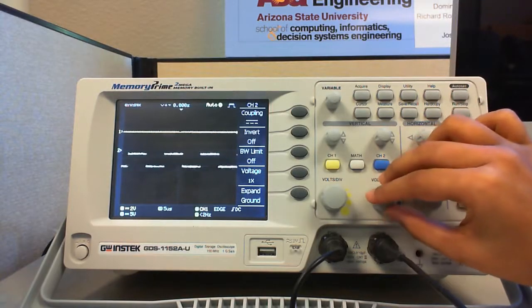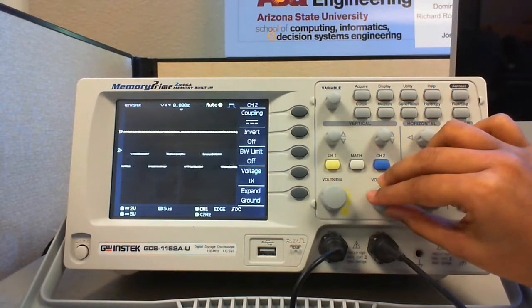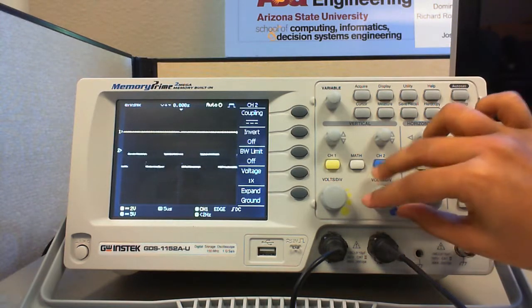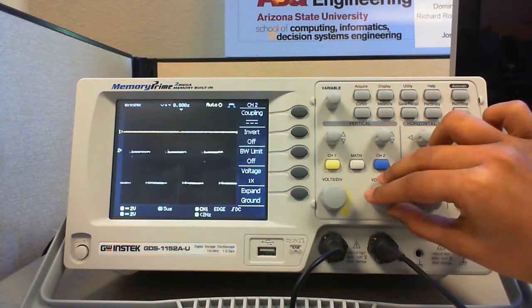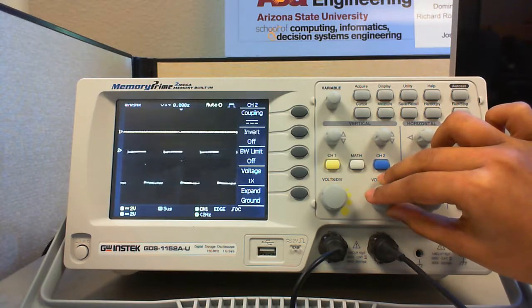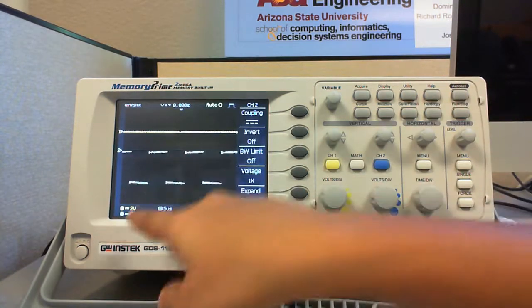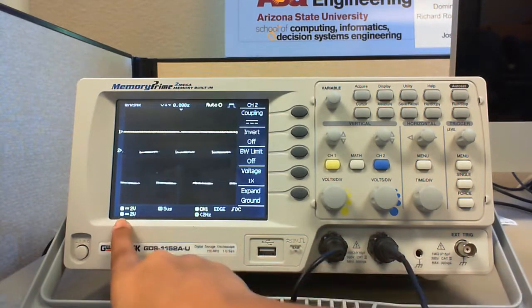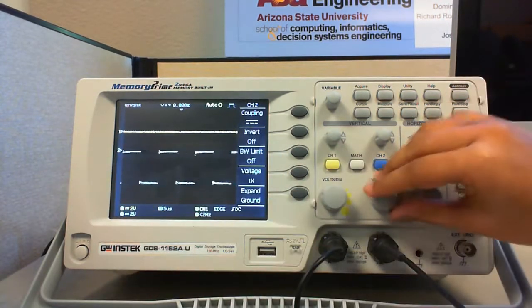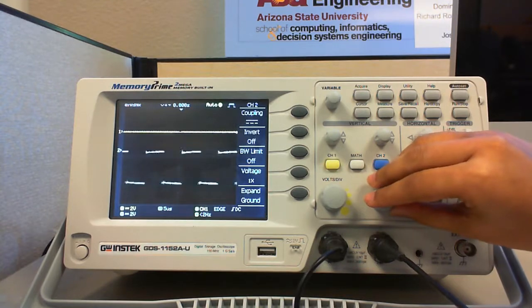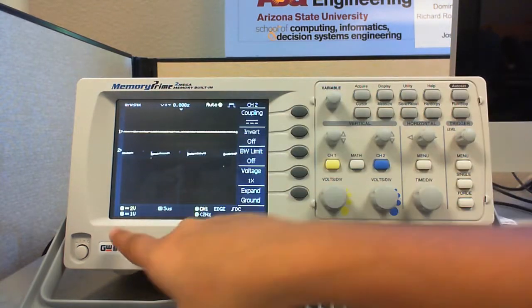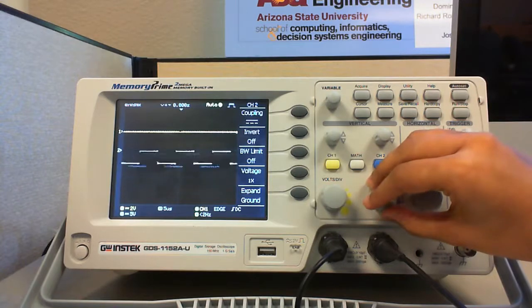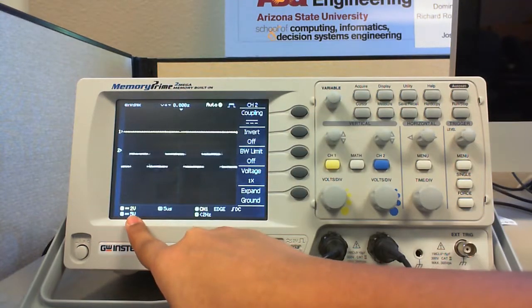Volts per division control knob is used to set a vertical scale factor. That is, you can increase or decrease the amplitude of the signal, scale it to a factor of your choice. Now, the signal is scaled to a factor of two volts, which is displayed on the leftmost corner of the screen. Now, if you rotate the control knob, you can see that it has changed to one volt. Now, it has changed to five volts.